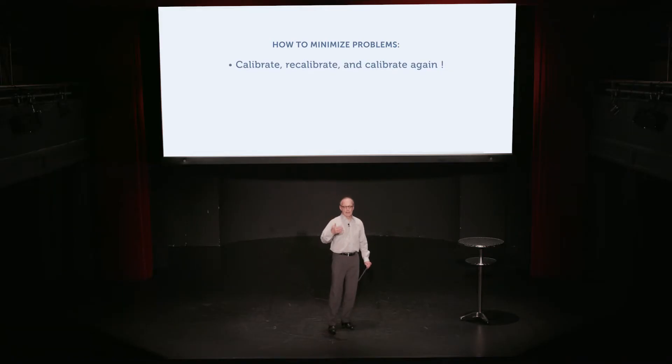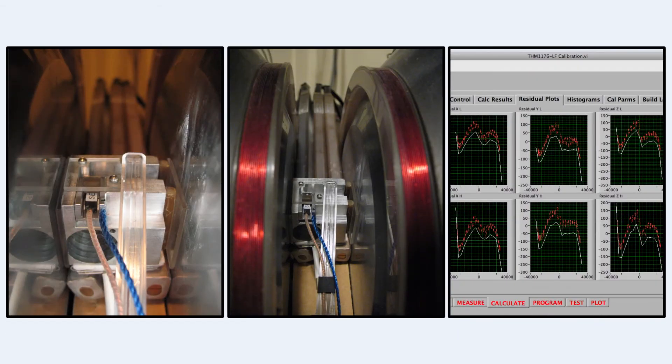You also need to calibrate at at least two temperatures to compute the temperature coefficients of both the gain as well as the offset, because both of those will vary with temperature. Two or three-axis sensors require calibration on each of the axes, plus additional measurements to determine any angular errors.